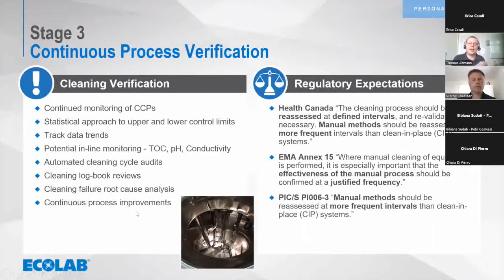You know exactly how it should run. For example, if you're running 10 minutes of rinsing after cleaning the equipment, and after 2 minutes you already identify that the water conductivity target is reached, why continue rinsing 8 minutes more, spending water and sending it down the drain, when you already know there is no change in the process anymore?